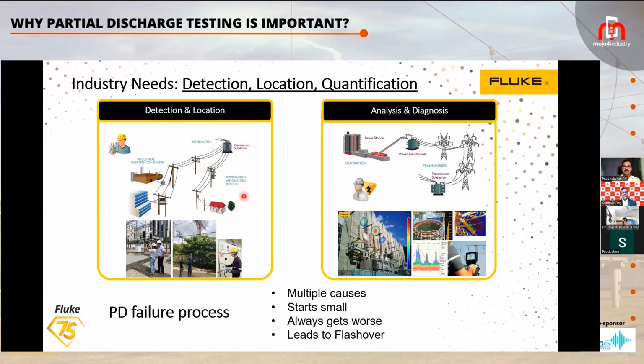When it comes to PD, you have to have PD detection and localization, locating PD in your utilities. You also need analysis and diagnosis, even in the manufacturing segment of transformers and motors. You need quality testing with partial discharge, otherwise you will end up sending out a lot of faulty equipment.